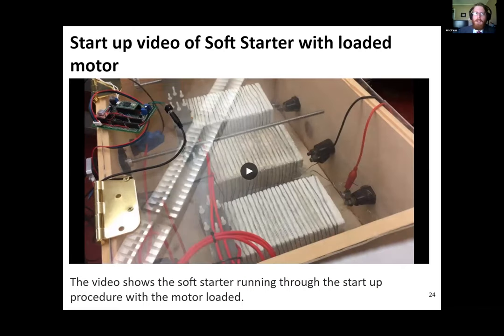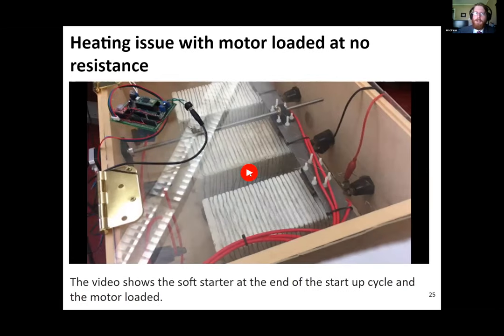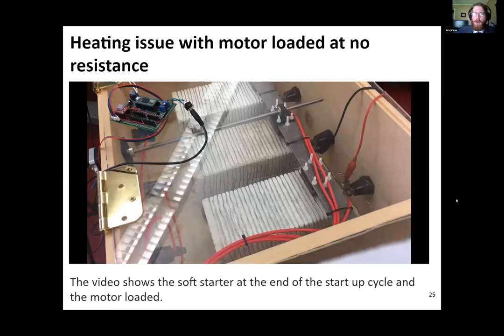In this last video here, before our live demonstration, if I could draw your attention to the red alligator clip on the right side of the screen. If you watch the small piece of wire right next to that, you'll see it glows red hot very briefly. We did a number of tests with the testing at fixed full resistance, fixed low resistance, and we discovered that we only see this issue as the wiper bar approaches the lower end of our rheostat, which would be the area of least often operation.